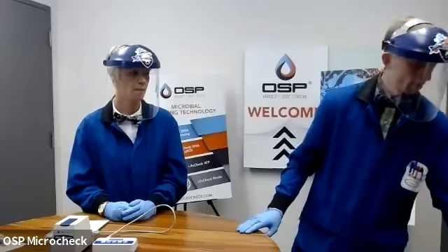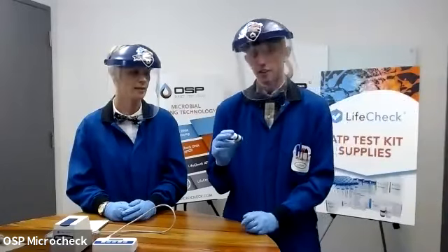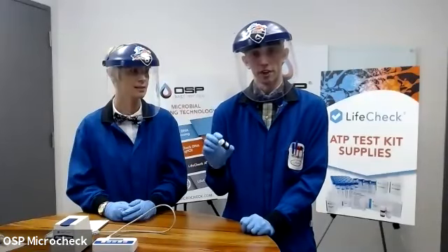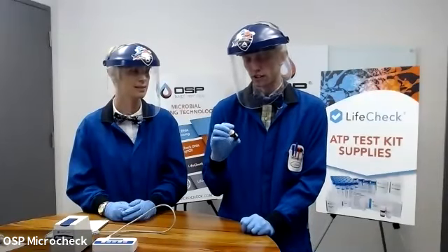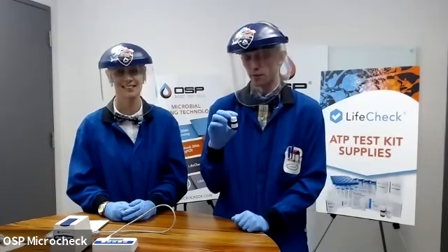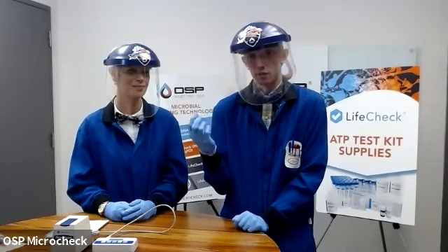This question for the most part was answered, but just to reaffirm, what is the average life expectancy of the enzyme once you activate it with the buffer? Once I activate it with the buffer, it's all going to depend on how often you use it, but if you're treating it nice, it's in the fridge right after testing and doesn't get heat shocked at any moment. And by heat shocked, I mean, again, 30 or 40 degrees centigrade for a period of time. You could expect this to last for months.